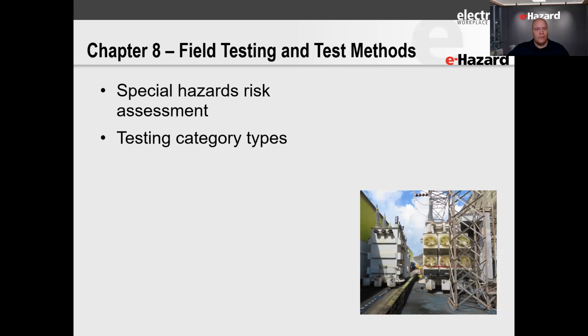Basically, type 1 is an online test, meaning it's energized; type 2 is an offline test, meaning it's de-energized. When you see the letter A added to the test type number, that's just an enhanced version, meaning it's above and beyond what we normally do for equipment like that. Some things you have to do, some things are more optional, but it puts us in a better place.